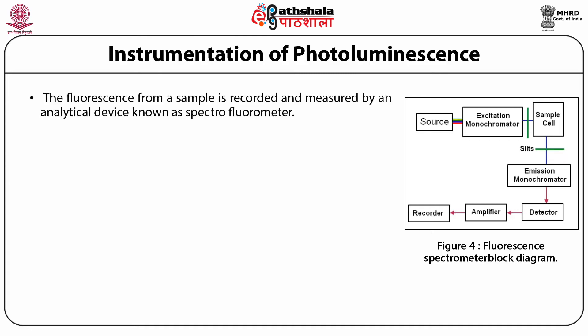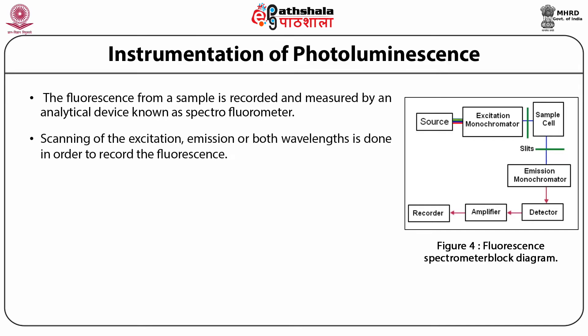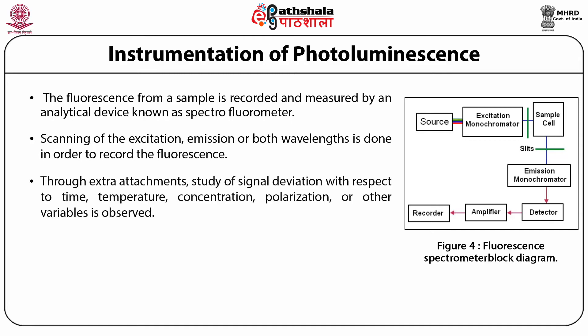Let us study the instrumentation of photoluminescence. The fluorescence from a sample is recorded and measured by an analytical device known as a spectrofluorometer. Scanning of the excitation, emission, or both wavelengths is done to record the fluorescence. Through extra attachments, study of signal deviation with respect to time, temperature, concentration, polarization, or other variables is possible. The block diagram of a fluorescence spectrometer is represented.